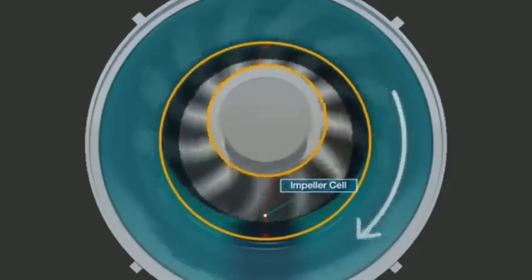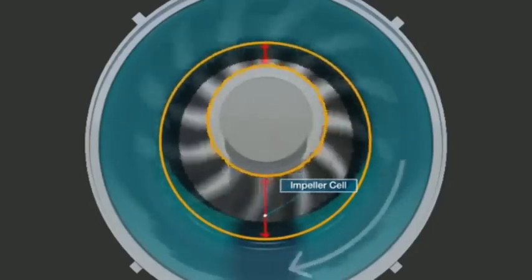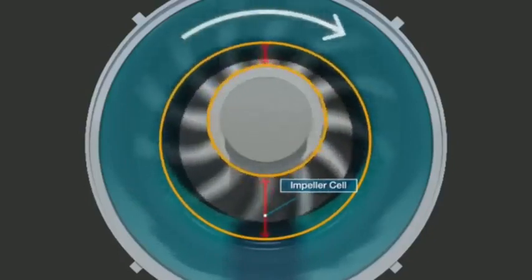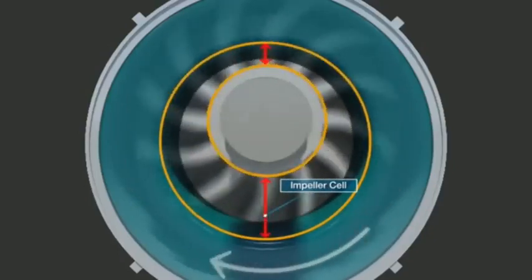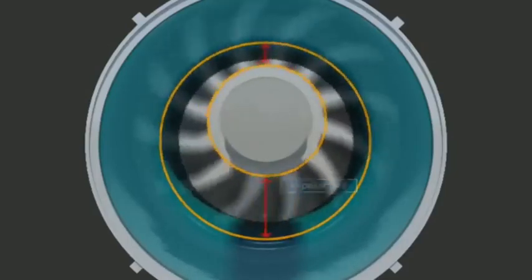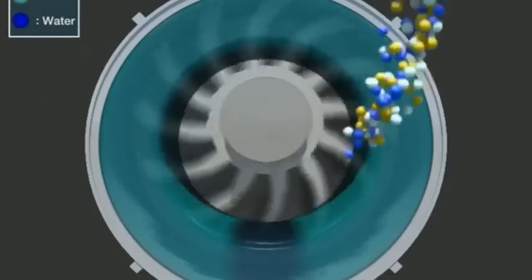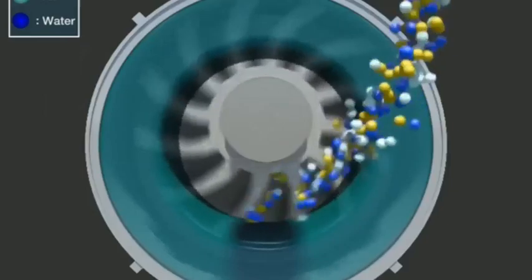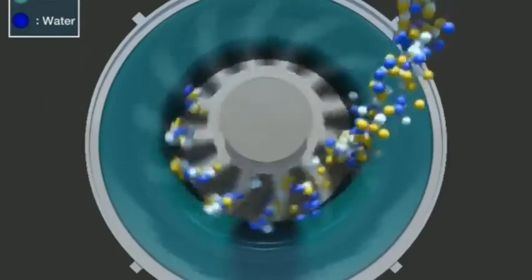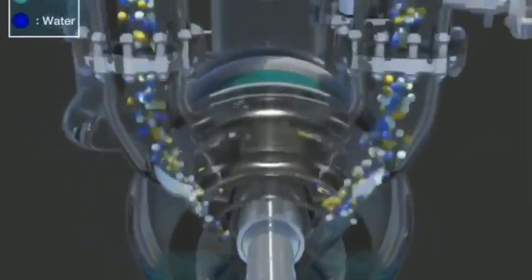of the centrifugal force. The liquid ring, which is caused by the circulation of the impeller, causes the capacity differentiation between the impeller and the inner wall because the impeller is located at the biased position inside the casing. This lets the air and gas from the system be sucked inside by making a vacuum with the pressure reduction caused by the capacity increase of the impeller cell at the inlet port.